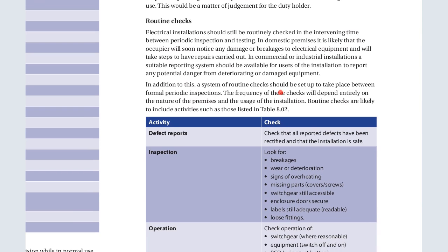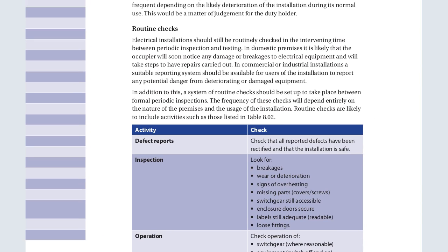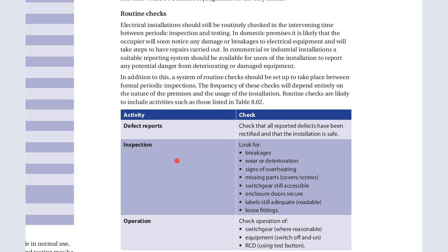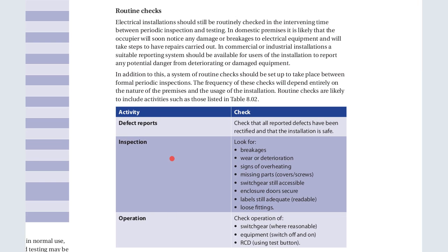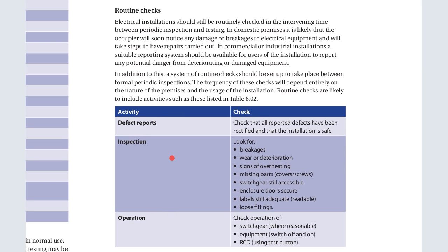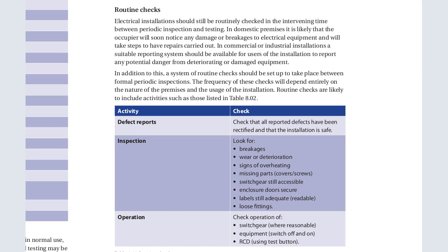Routine checks. Now, what are the routine checks? Electrical installations should be routinely checked in the intervening time between periodic inspection and testing. In domestic premises, it is likely that the occupier will soon notice any damage or breakage to electrical equipment and will take steps to have repairs carried out. In commercial or industrial installations, a suitable reporting system should be available for users of the installation to report any potential danger from deteriorating or damaged equipment.